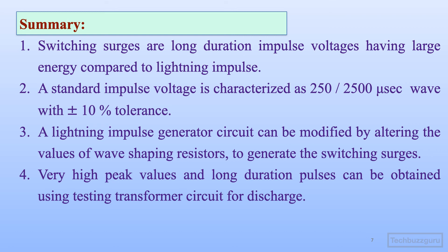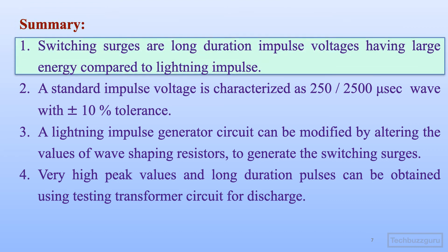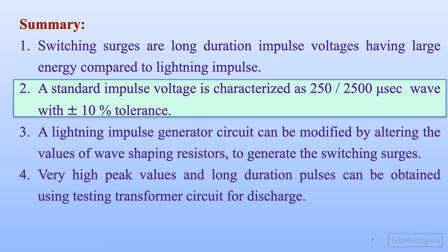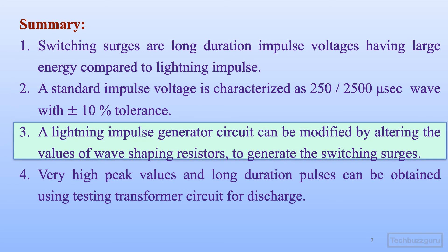Let us summarize what we have learned in this video. First and foremost, the switching surges are basically long duration impulse voltages having large energy when compared with lightning impulses. The standard impulse voltage is characterized as 250/2500 microsecond wave with plus minus 10% tolerance.